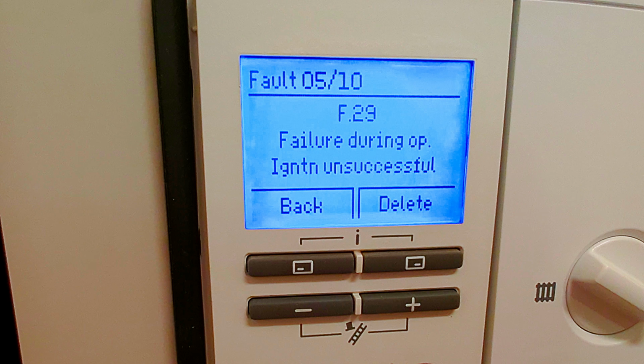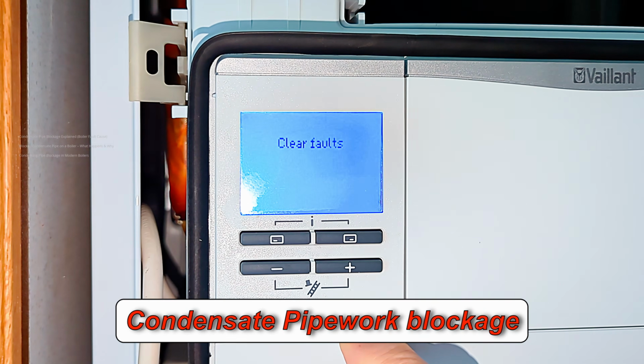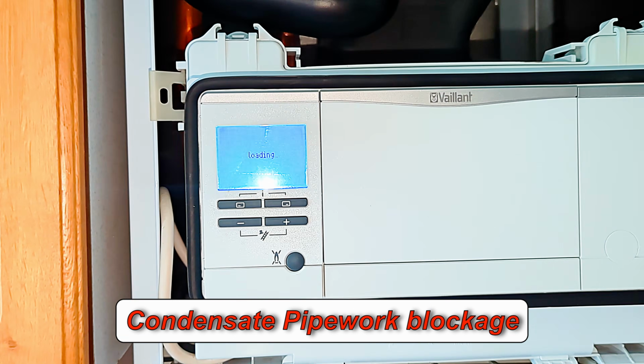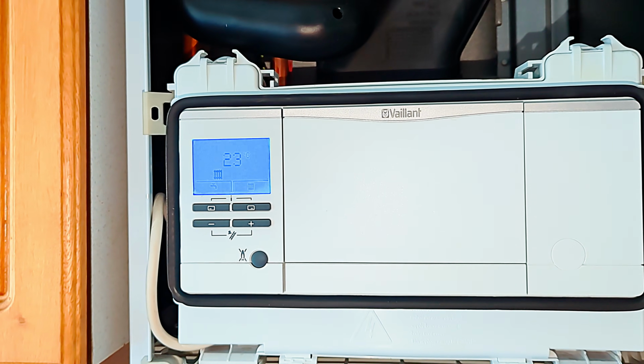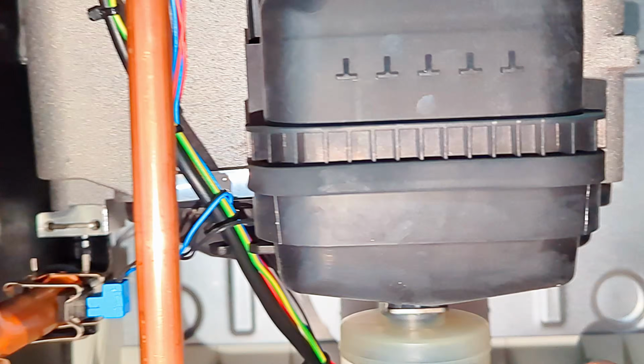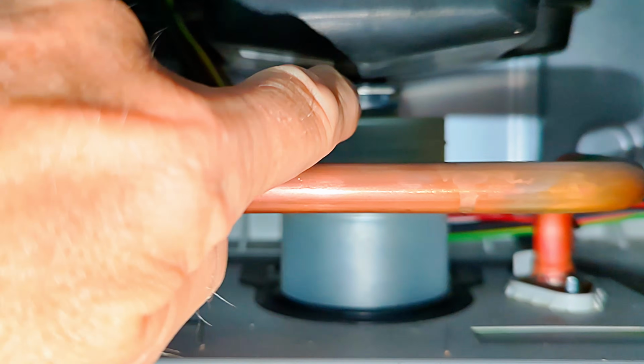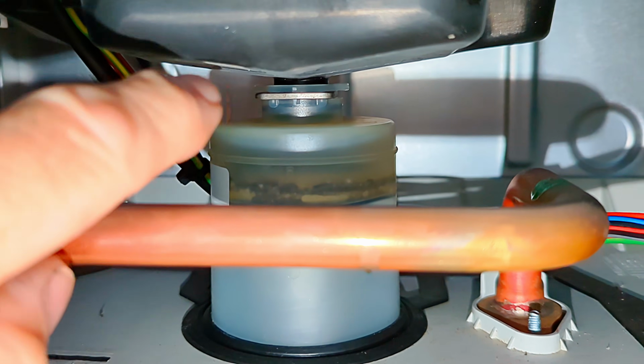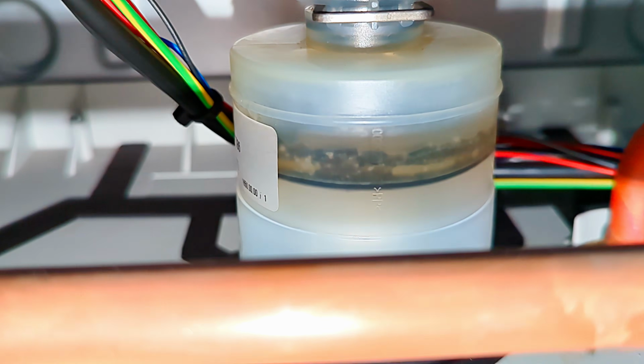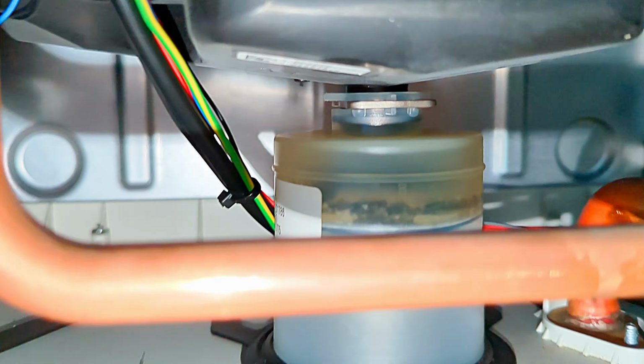And F29 is an ignition fault again. The boiler's been operating and it's gone off for some reason. You might get either or both of these fault codes coming up if you have this blockage. Now the reason this boiler has failed to start up is the condensing trap has become blocked and the bottom of the main heat exchanger has become full of water. So air can no longer flow through it, and so it's tripping out with the F28 fault.